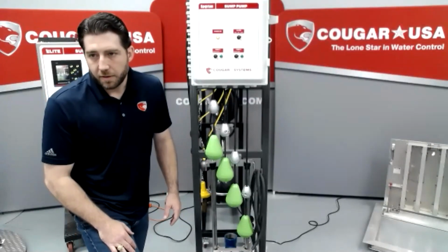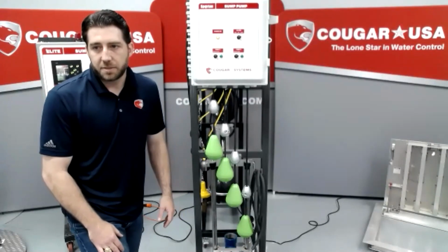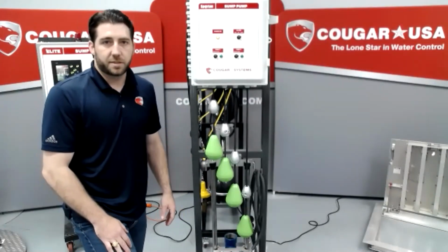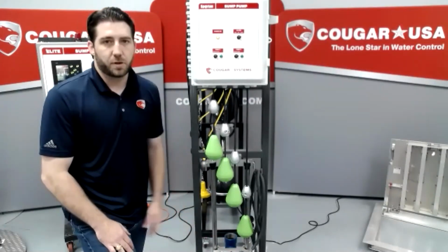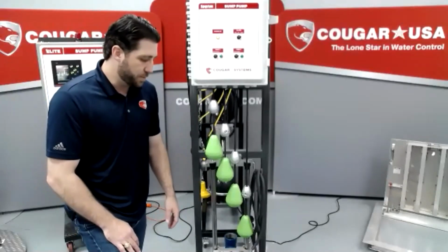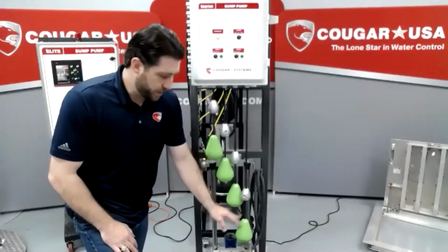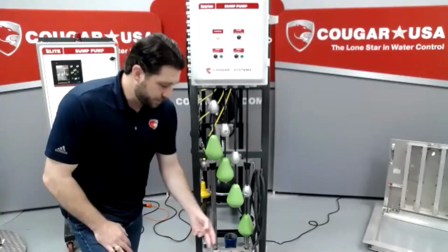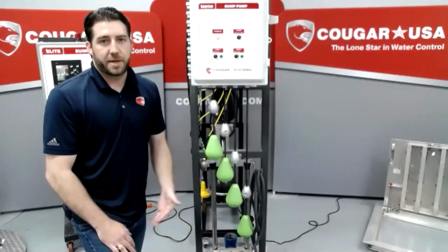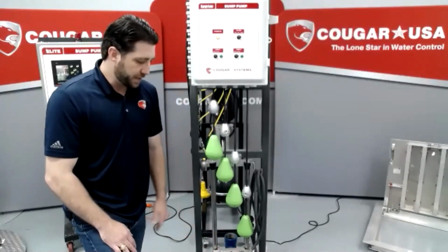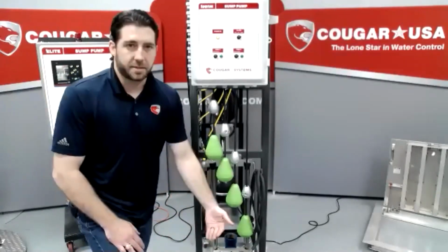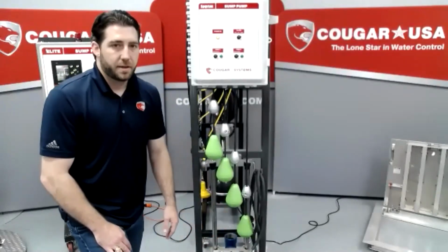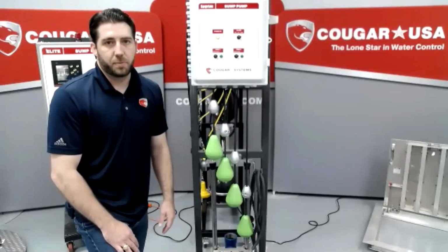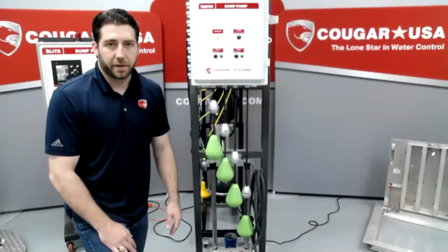What is the minimum water level that needs to be maintained on the pump itself to keep the motor cool? So that's a good point. These pumps are using the water to help cool the motor. So we're showing it here stopping above the pump, but really the worst case would be about halfway down the motor. If the pit's big enough where you can stop it at the top of the pump, that's even better. But I would say halfway down the pump would probably be the lowest that you would want to go if you had to.